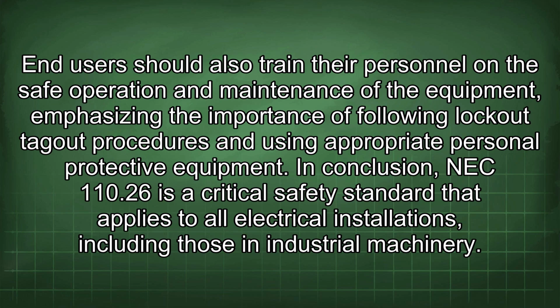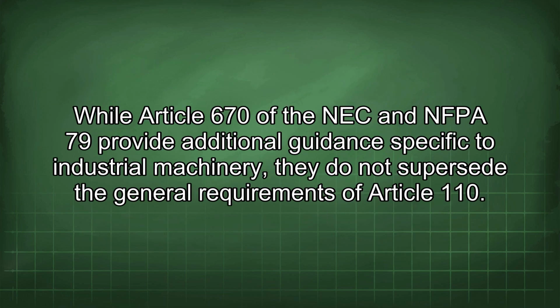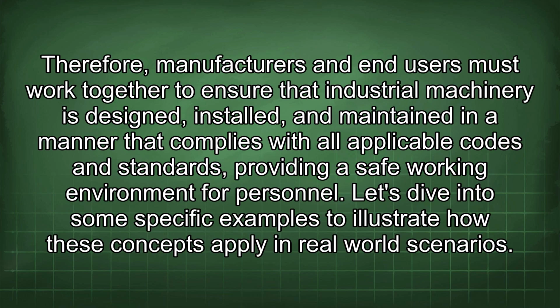In conclusion, NEC 110.26 is a critical safety standard that applies to all electrical installations, including those in industrial machinery. While Article 670 of the NEC and NFPA 79 provide additional guidance specific to industrial machinery, they do not supersede the general requirements of Article 110. Therefore, manufacturers and end users must work together to ensure that industrial machinery is designed, installed, and maintained in a manner that complies with all applicable codes and standards, providing a safe working environment for personnel.